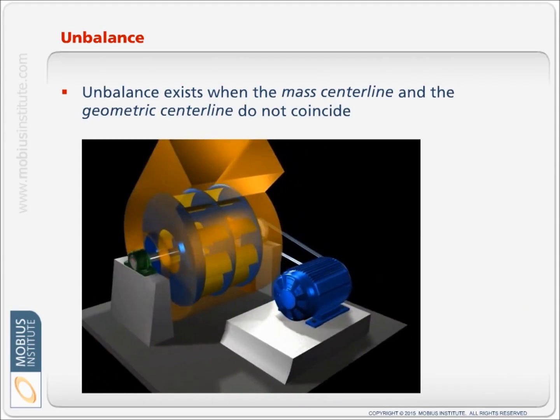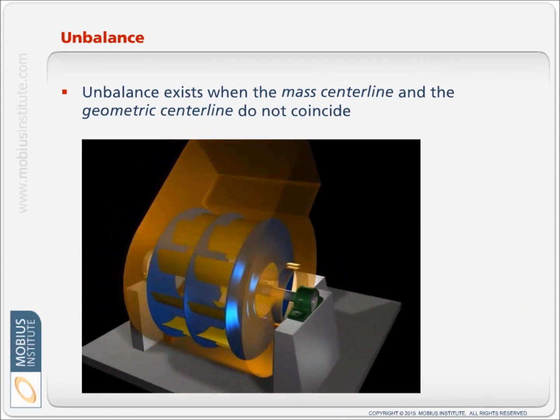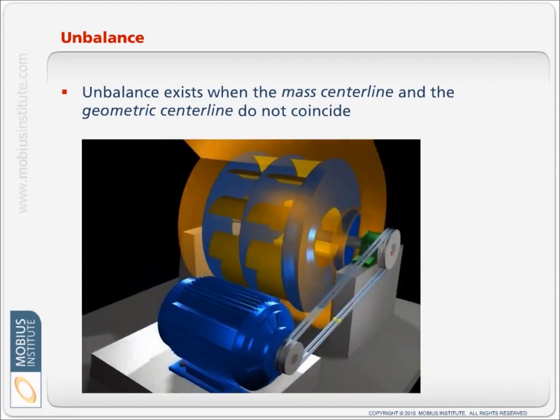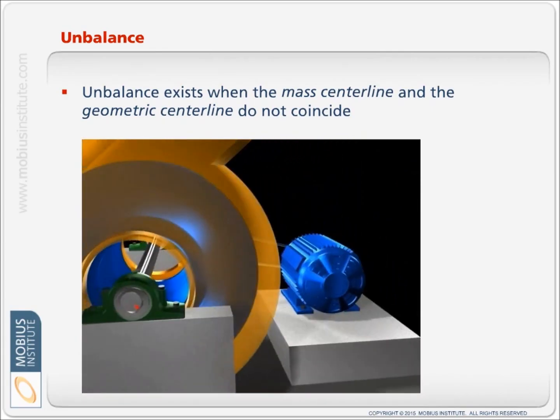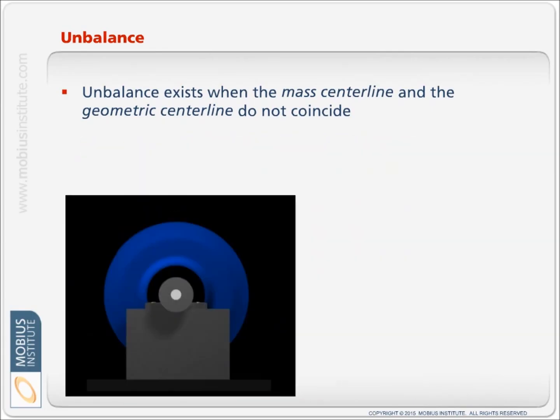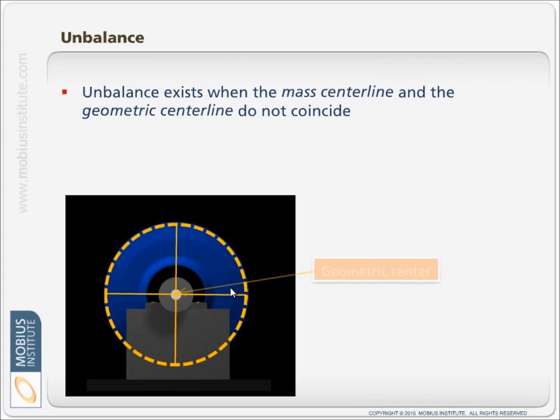Unbalance exists when the mass centerline and the geometric centerline do not coincide. The geometric centerline is the center of geometry, which for our fan should be right through the center of the shaft. If we draw a circle around it, it should, if the machine is designed properly, go straight through the center of our shaft — and that is where it also wants to rotate. That is our geometric centerline.